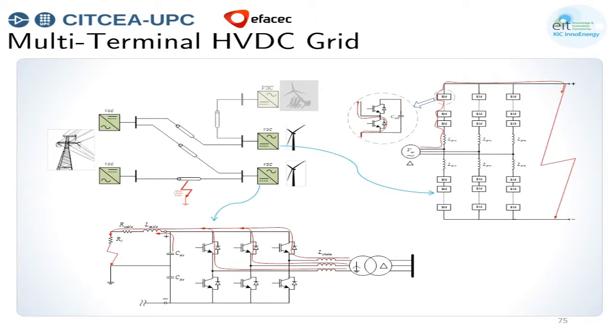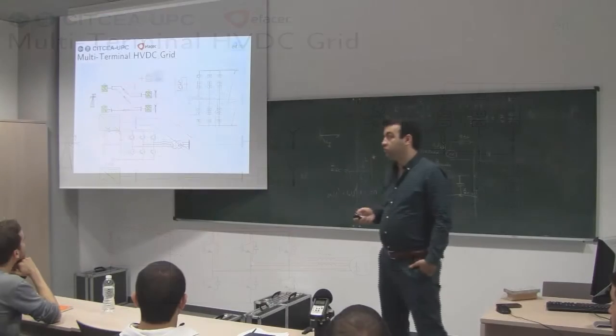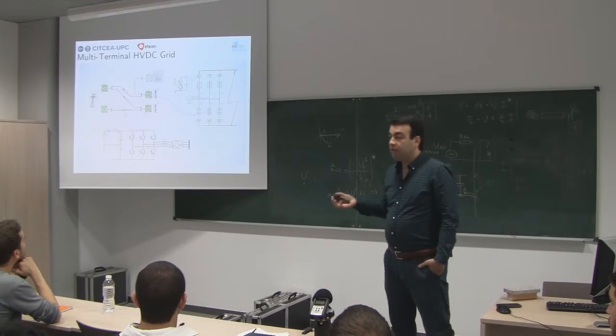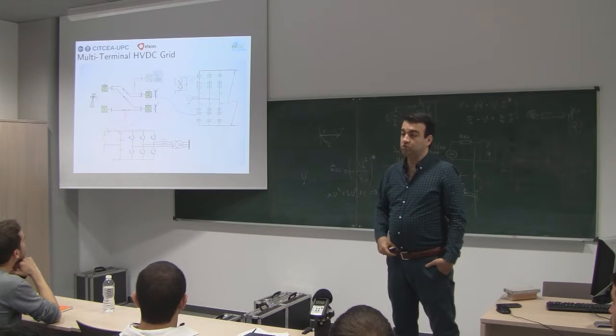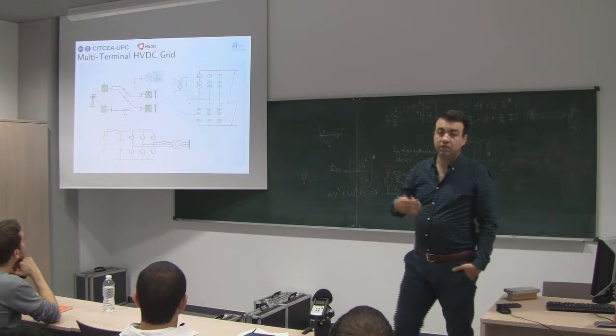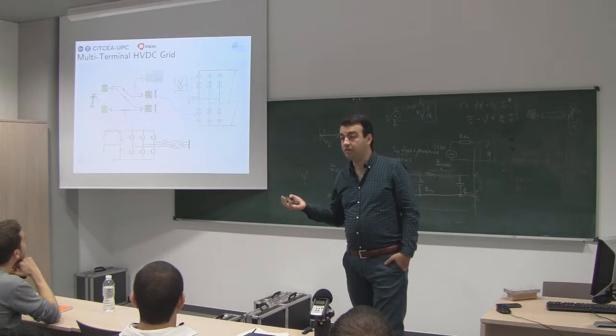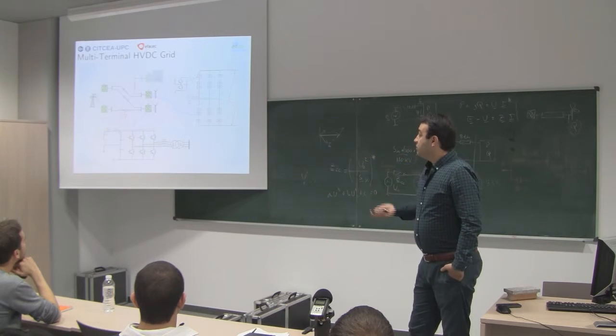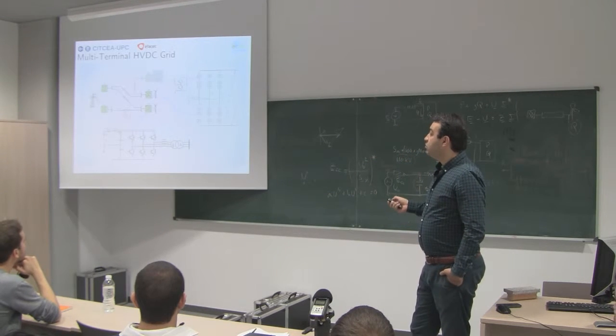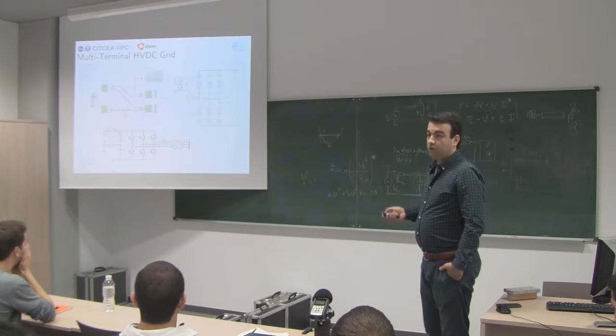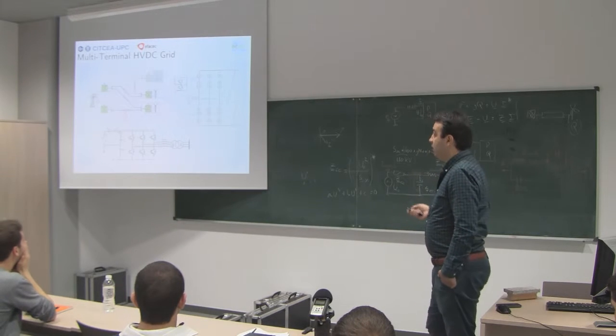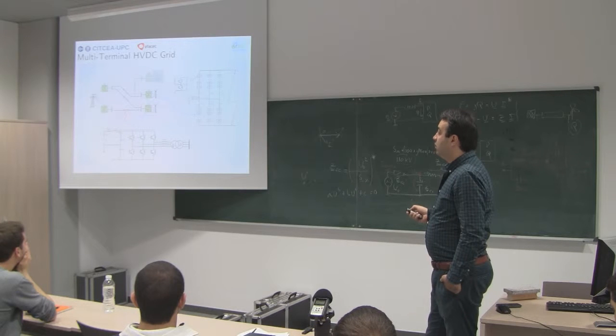But what is the drawback of this technology? It is identified that there can be protection issues. The protection issues in a multi-terminal HVDC grid are much more complicated than in the AC one. I will introduce the topologies of HVDC converters; I have two figures here.